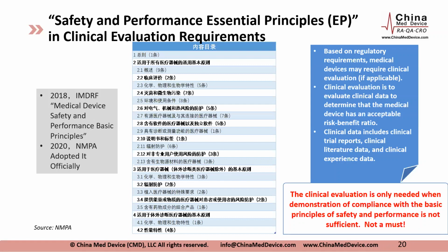Based on these essential principles, you decide, okay, should I do an evaluation? Should I do a clinical trial? Because if you meet this essential principle guidance, you may not even need a clinical evaluation. This is accepted by NMPA. So that's why I start off with this EP principle.